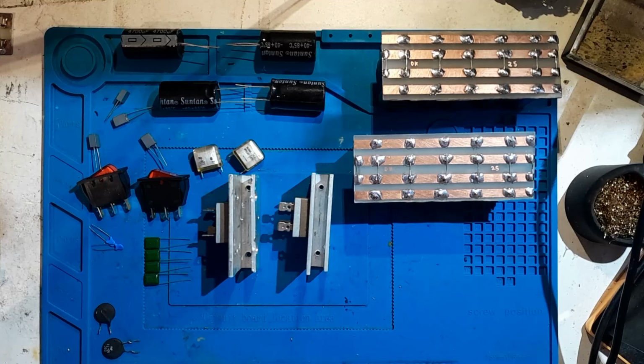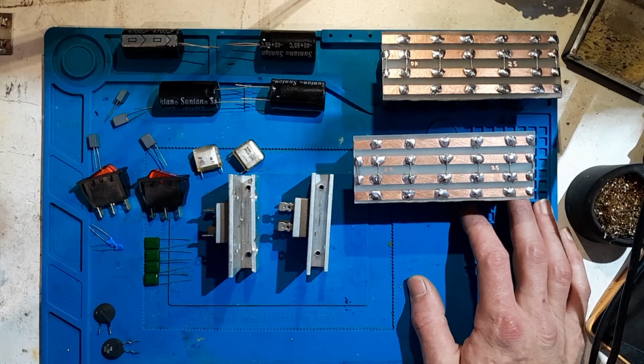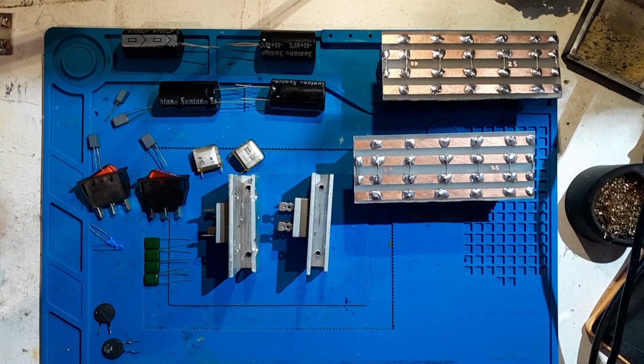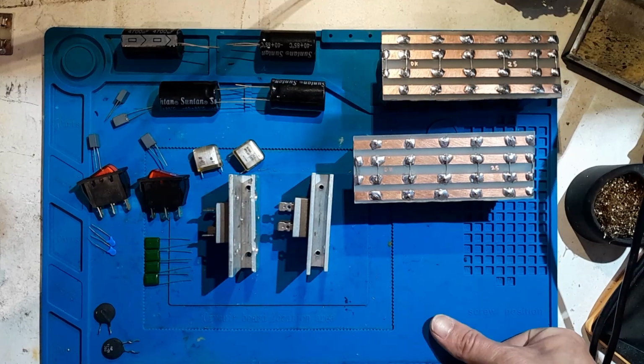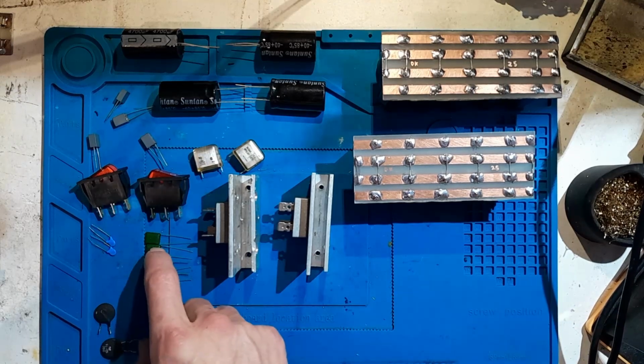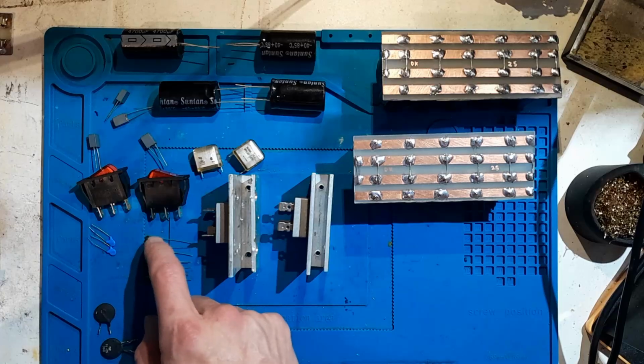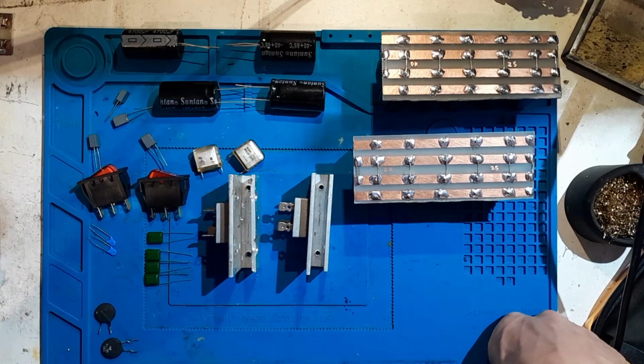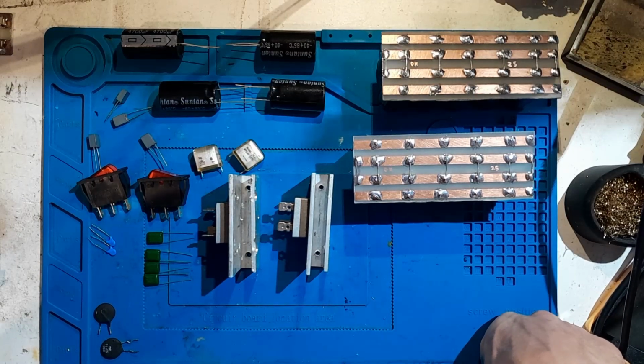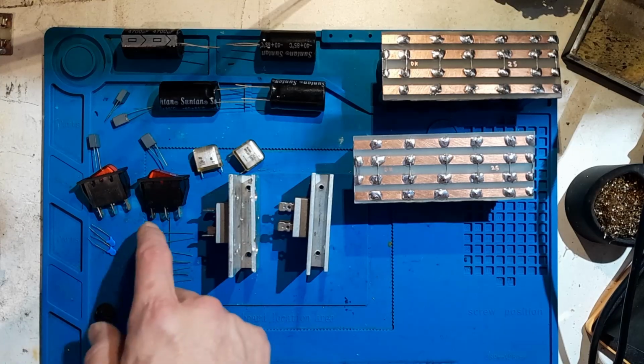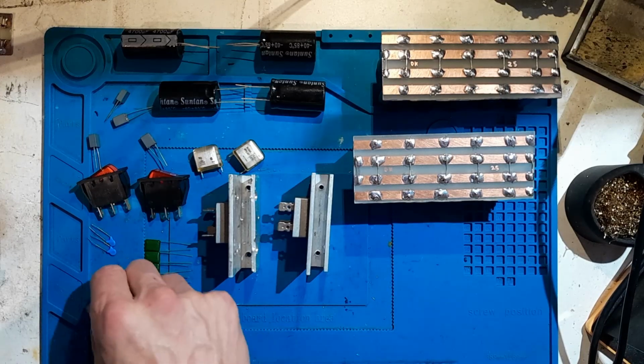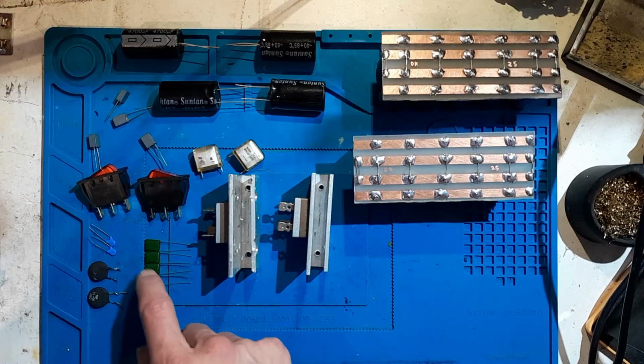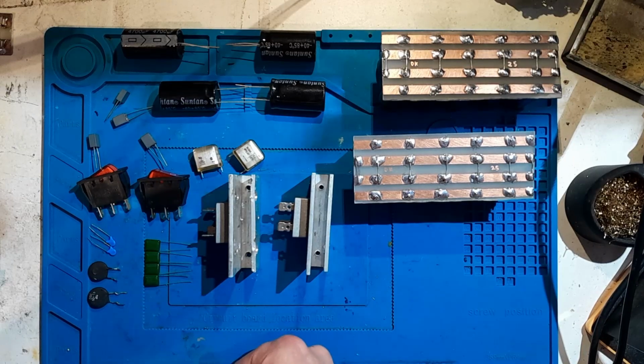Depending on the type of capacitor, you probably will need a resistor. With snubbering with a capacitor, the R gives you your damping factor, or adds to it. Now, these capacitors happen to have an already high ESR, so it's basically like there's a resistor in series with them. That's why, in a lot of situations, for small damping situations, you can just put one of these straight across the transformer. If you had a lower ESR cap, you'd probably want to use a resistor in series, if that makes sense.